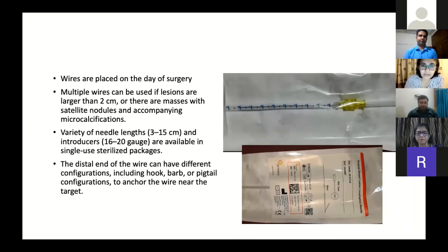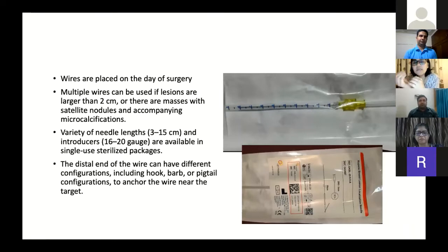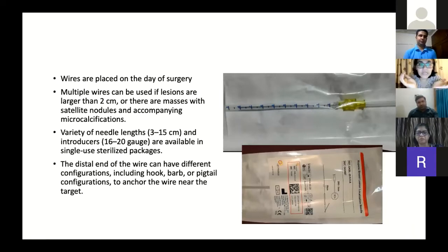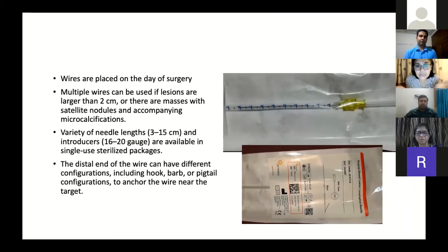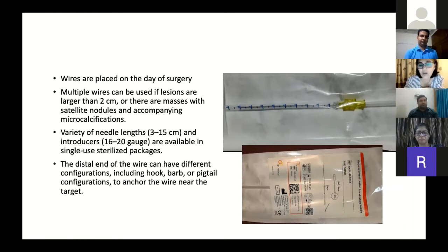Multiple wires can be used — for lesions larger than 2 centimeters to bracket the lesion, for masses with satellite nodules, or when there is an accompanying microcalcification. There are a variety of needle lengths and introducers ranging from 3 to 15 centimeters in length and 16 to 20 gauge, all available in single-use sterilized packages. The distal end of the wire can have different configurations, but the commonest is a hook; they can also have a barb or pigtail configuration.